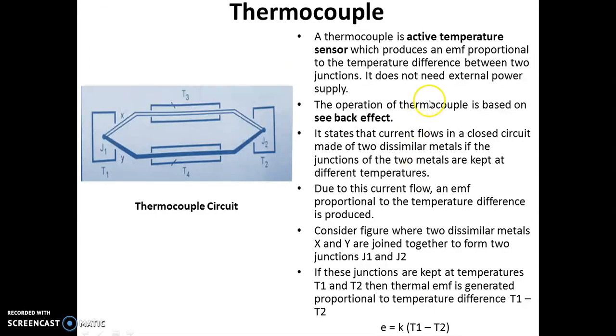Now let us see one more temperature sensor — the thermocouple. Thermocouple is an active temperature sensor, unlike thermistor or PRT which are passive types. Being an active sensor, it produces an EMF due to changes in temperature and does not need any external power supply. Thermocouple operation is based on the Seebeck effect, which states that current flows in a closed circuit made up of two dissimilar metals if the junctions of the two metals are kept at different temperatures. Due to this current flow, an EMF proportional to the temperature difference is produced.